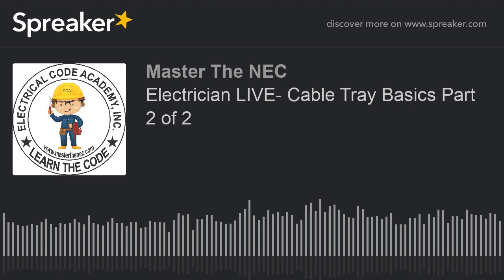So we talked about all those items, and now we're going to move into what I promised in part 2, which is dealing with ampacities of the conductors that are put in that cable tray. Of course, we've got multiconductor cable and single conductor cables. And as you remember from part 1, single conductor cables, or now single insulated conductors, can be in a cable tray as long as it's an industrial establishment.